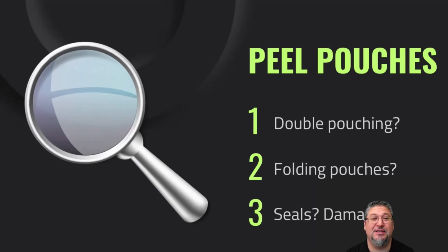If you're double pouching, make sure that you have the same manufacturer and that manufacturer has a statement in their IFU that states that it's okay to double pouch. Surveyors have picked up on the fact that a lot of hospitals use multiple vendors for pouches. When you're putting manufacturer A inside manufacturer B and double pouching, no one has tested that. There is no testing data that says that's okay. So you have to make sure it's the same manufacturer and that manufacturer has a statement on double pouching.